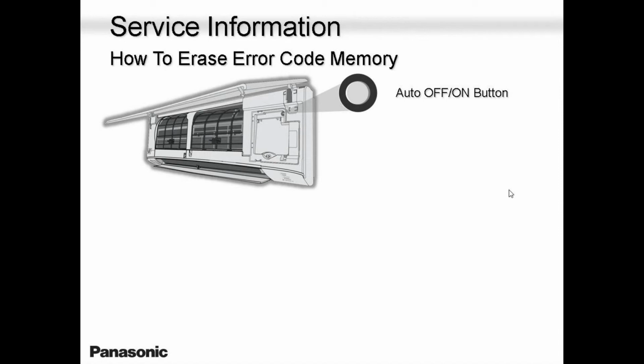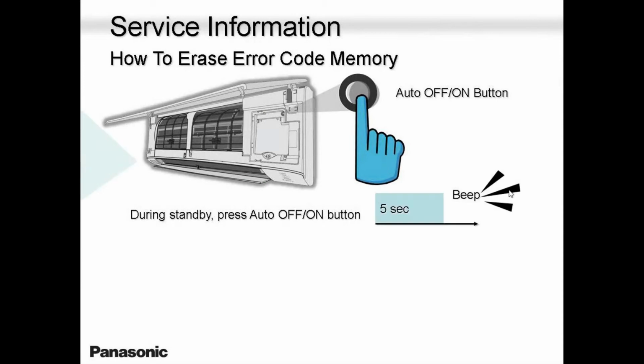Now, sometimes our guys go on a maintenance call, a simple maintenance call, and the unit is working fine, no problem. But for some reason, they go and check the error code. And then they call me and they say, hey, Paul, I got this error code, H99, or H something, or F something. And I asked them, is the unit running? And he says, yeah, the unit is running perfectly well. I asked him, why did you check the error code? Oh, I'm on a maintenance call.